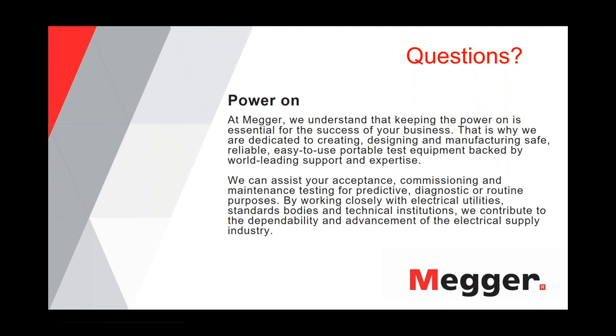All right, excellent. Henning, what should be the test step duration and how long do you hold the voltage for each step? Well, the test step duration is defined by the number of test points you will set up for each test voltage. And typically, you want to have at least 5 test points per voltage step. Now, each test point has to be long enough to get a steady reading. So typically, maybe 20, 30 seconds should be enough time to get a steady reading per test point. So if you have 5 test points, you can say 5 times 30 seconds. It's basically about 2.5 minutes per voltage step. And then you do this for all three voltage points, right?